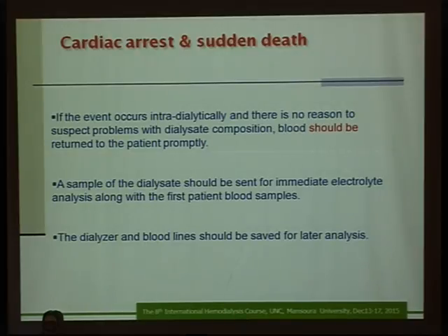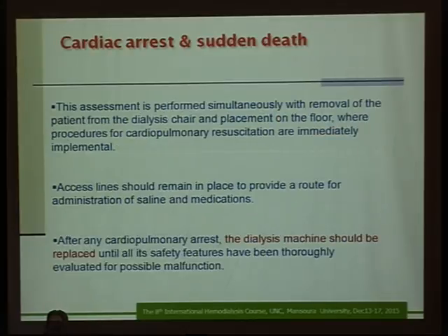If cardiac arrest occurs during the dialysis session and there is no reason to suspect a problem with dialysate composition, blood should be returned to the patient promptly. A sample of dialysate should be sent for immediate electrolyte analysis along with the patient's blood samples. The dialyzer and bloodline should be saved for later analysis to detect the cause.